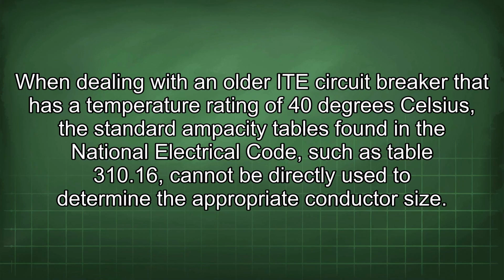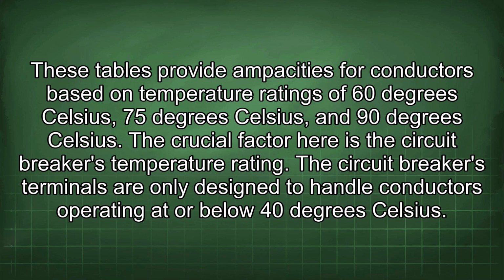When dealing with an older ITE circuit breaker that has a temperature rating of 40 degrees Celsius, the standard ampacity tables found in the National Electrical Code, such as Table 310.16, cannot be directly used to determine the appropriate conductor size. These tables provide ampacities for conductors based on temperature ratings of 60 degrees Celsius, 75 degrees Celsius, and 90 degrees Celsius. The crucial factor here is the circuit breaker's temperature rating.